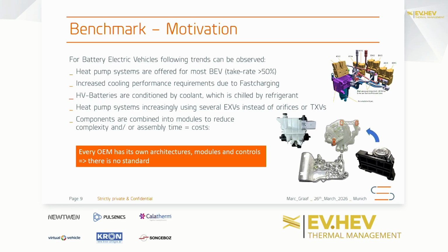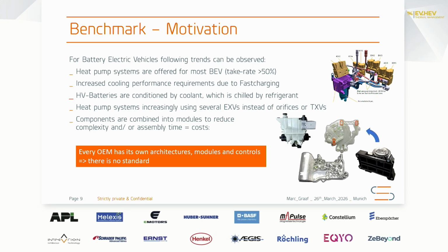So those are, let's say, the most common architectures in general, but in the details there are, of course, several differences. Some older systems were using orifices or TXVs as expansion organs, so that you don't have any means to control it, and that usually led to a situation that at negative ambient temperatures the system was shut off, and you need an electrical heater to heat up the cabin.